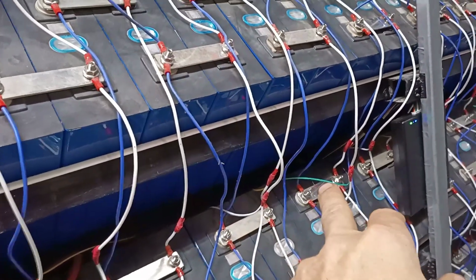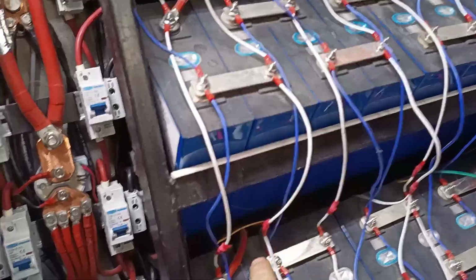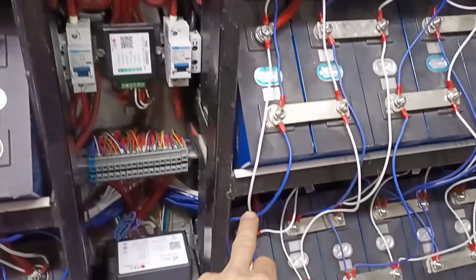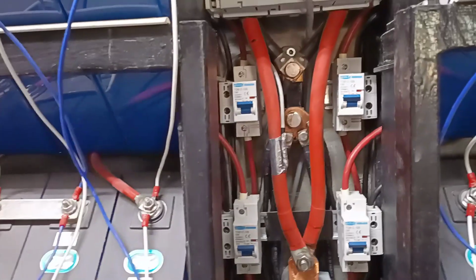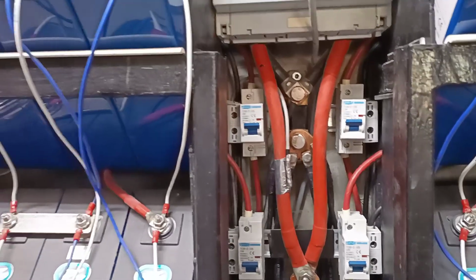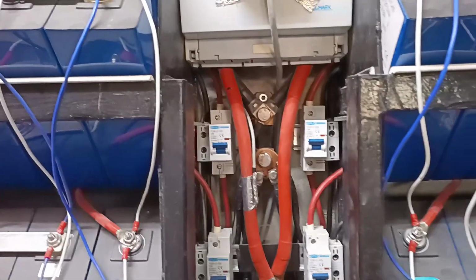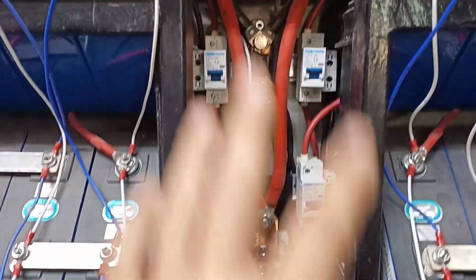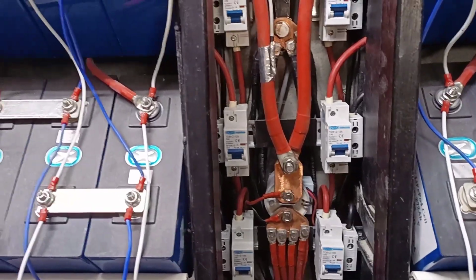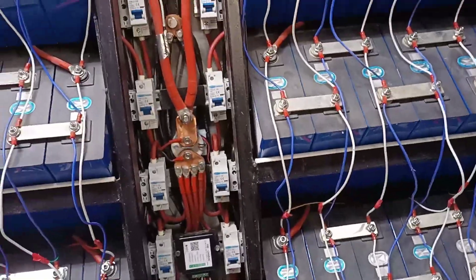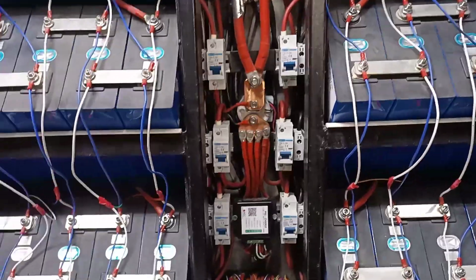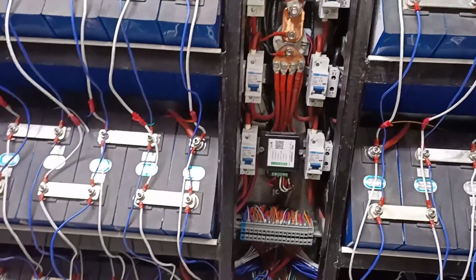Now the cable length is actually one meter longer than if the negative had been on this side. That's not a big deal, but maybe the shunt measurement for the electricity passing through the battery bank is a little off. I actually see a small measurement difference here, maybe because of the resistance of this longer cable—but it's not a big deal at all.